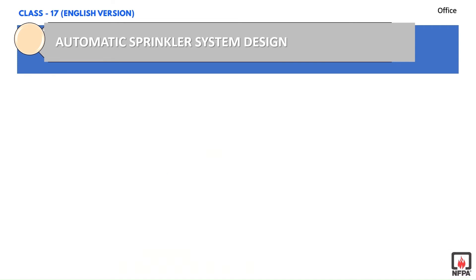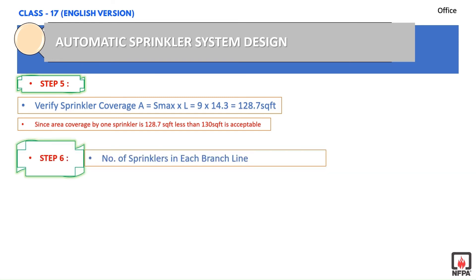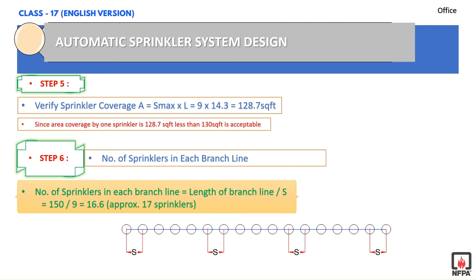Continuing Step 5, we cross-verify the coverage area of one sprinkler using the same formula. We get approximately 128.7 square feet. Since 128.7 square feet is less than 130 square feet, our considerations are acceptable. Step 6: We calculate the number of sprinklers in each branch line by dividing the length of the branch line — 150 feet — by the maximum distance between sprinklers. By this formula, we identify 17 sprinklers in one branch line.